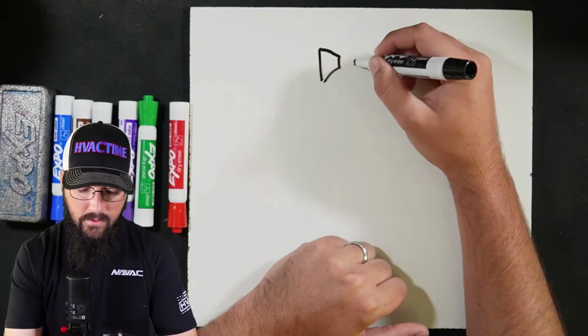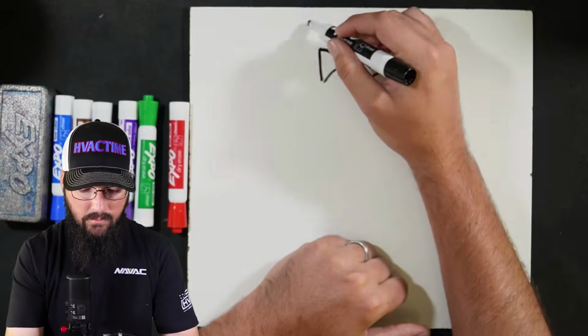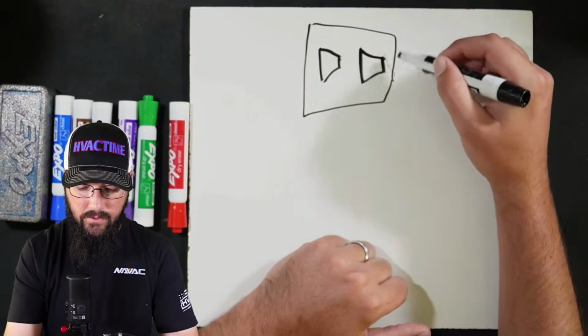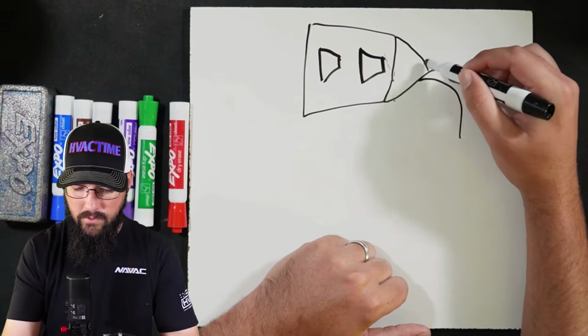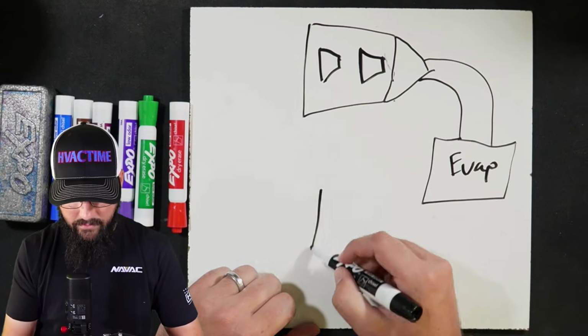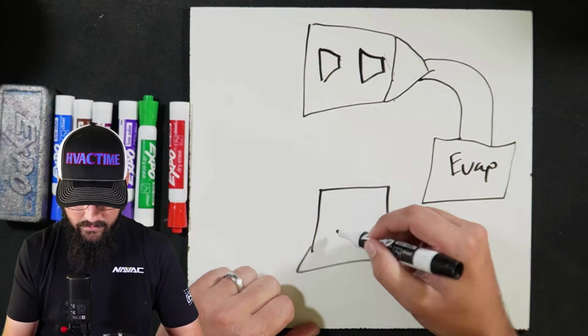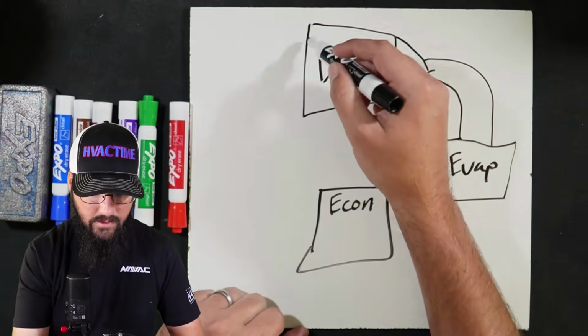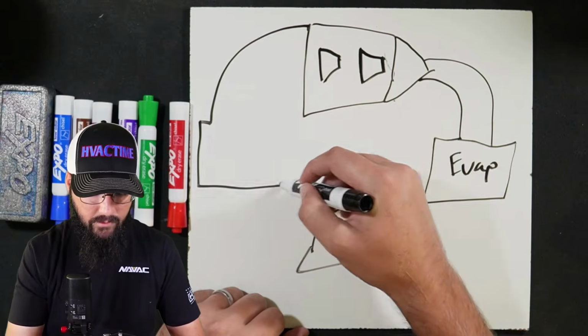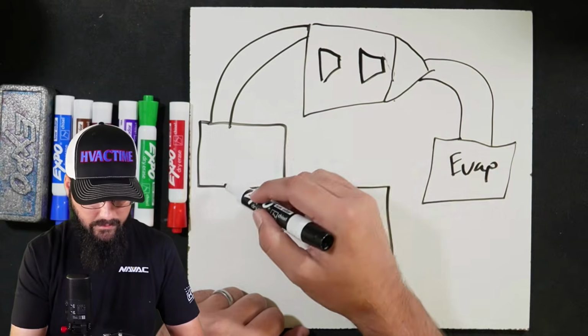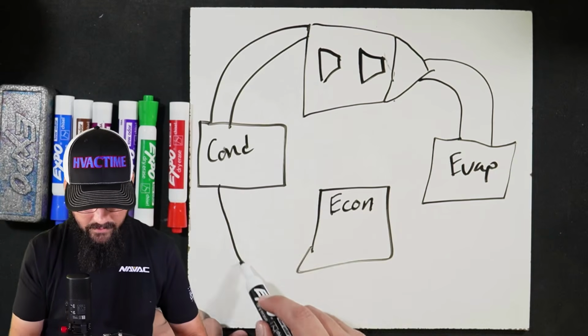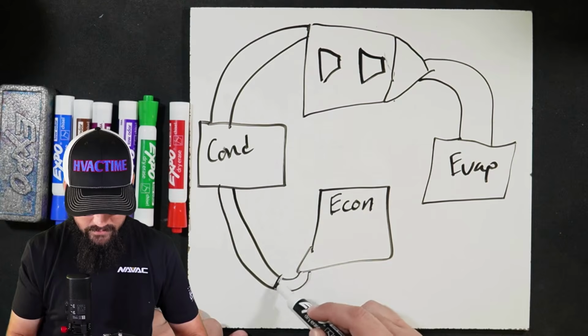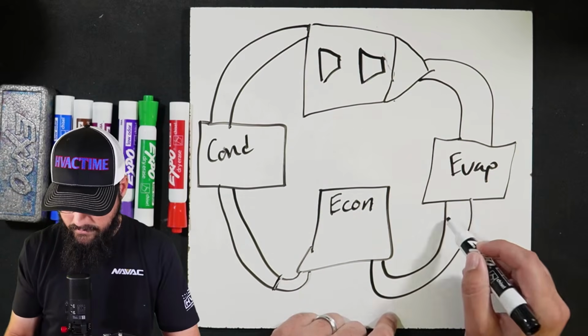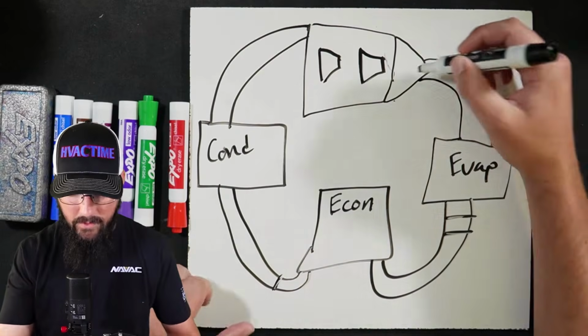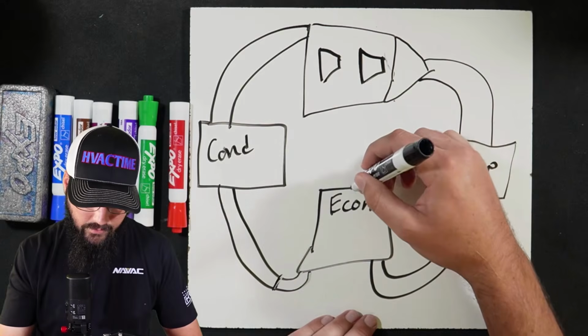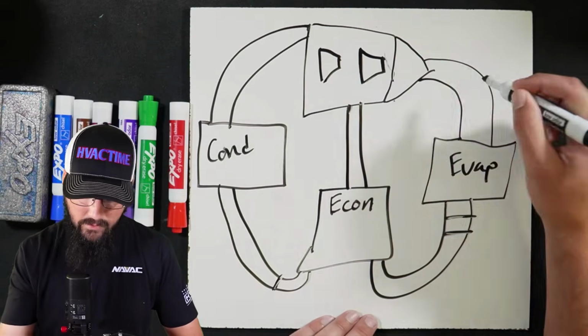So we have an impeller, and then we have our next impeller. We're going to put this inside the compressor. Okay, here's our nose cone. Come down into our evaporator. And then we're going to have our actual economizer. We're going to call this the econ. And then coming out of our discharge, I'm just going to draw this as a pipe up here. Very crude schematic, but you'll get the general idea. This is our condenser. And then our drop leg comes out into our economizer. Then we have another leg coming out into our evaporator. Guide vanes here. This particular one is just going to have a single pipe coming up right here. So everything's going to flow.